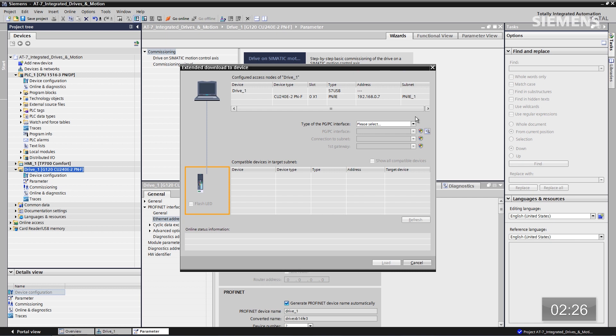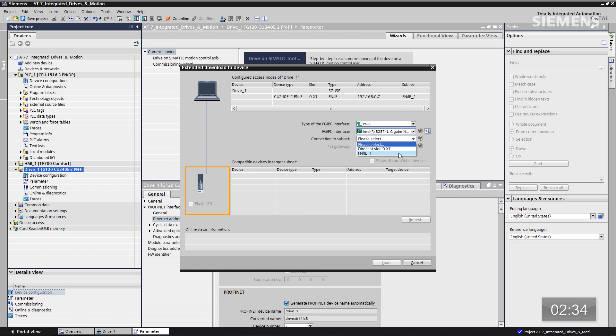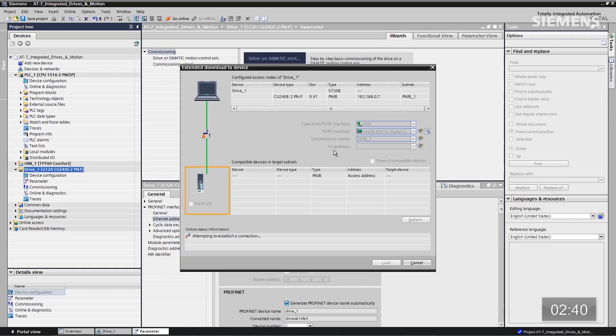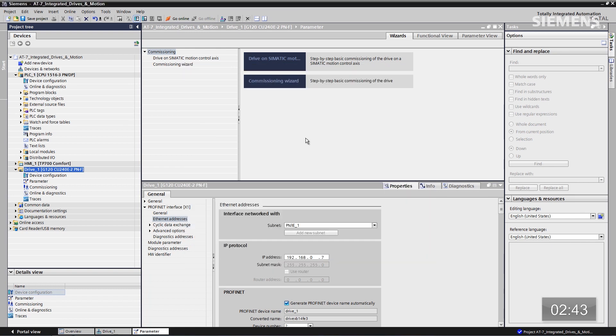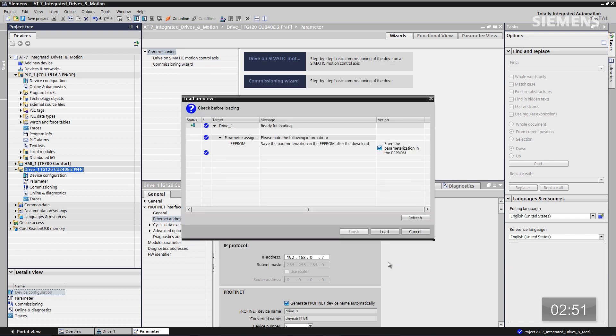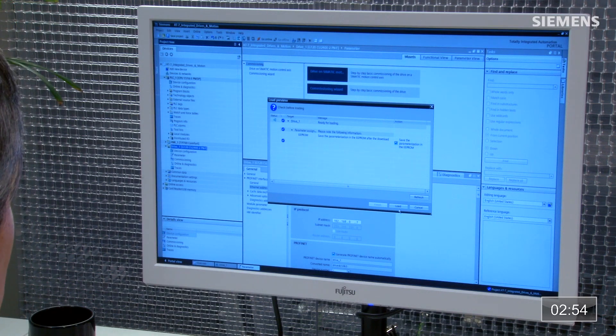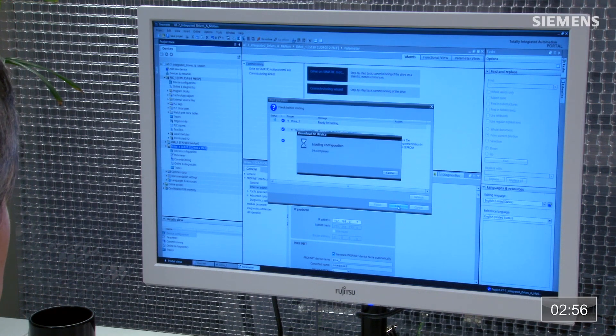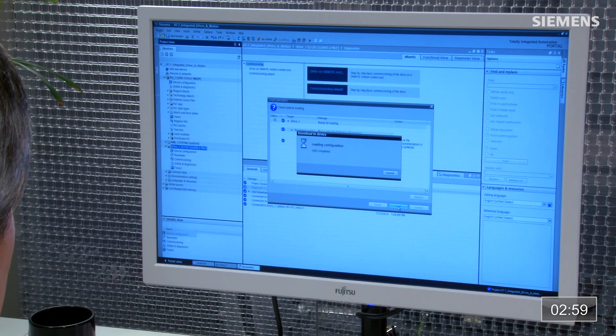Click on the download arrow button. Another dialog box pulls up. I can choose the network — it's going to be Profinet. Here's the network card, and the actual network is PN/IE_1. It's going to go out and search and find this G120 drive. Once it has found it, I can give focus to it and click Load. A dialog box asks: do you want to save this to the EEPROM? Yes, I do. Click Load again. Now it's going to compile everything and load to the G120 drive. Our load is complete and we have a fully parameterized drive.